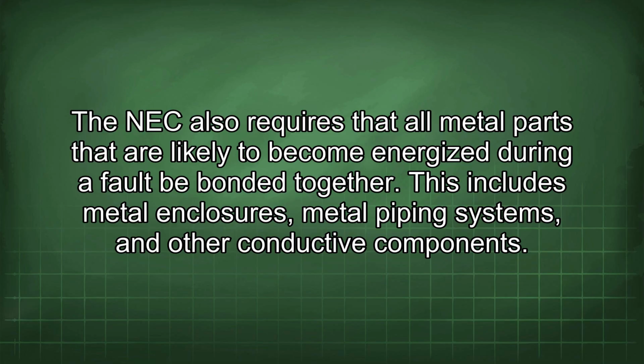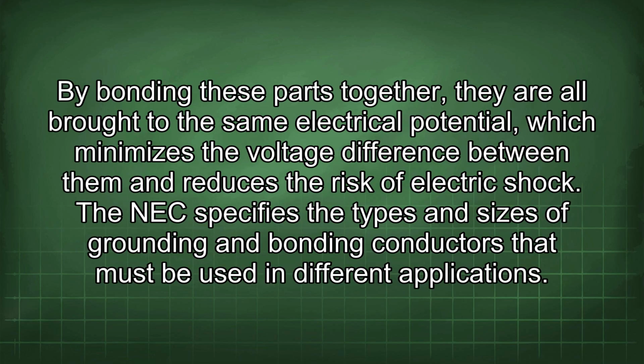The NEC also requires that all metal parts that are likely to become energized during a fault be bonded together. This includes metal enclosures, metal piping systems, and other conductive components. By bonding these parts together, they are all brought to the same electrical potential, which minimizes the voltage difference between them and reduces the risk of electric shock.